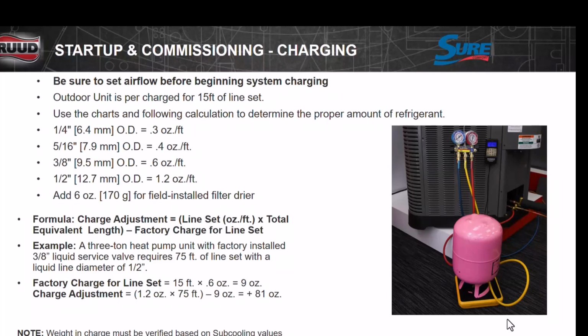How long should we let it sit? If we replace a compressor and weigh in the charge, I would leave that compressor powered up for a couple hours. A lot of the compressors, like the Copeland scroll compressor that runs off the contactor, not the variable speed one, have a single pole contactor, and it leaves that one line hot as an internal crankcase heater. It keeps the winding hot. So it's going to take a little while to get that liquid out of there.